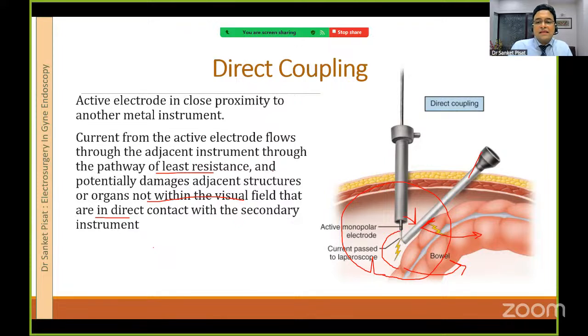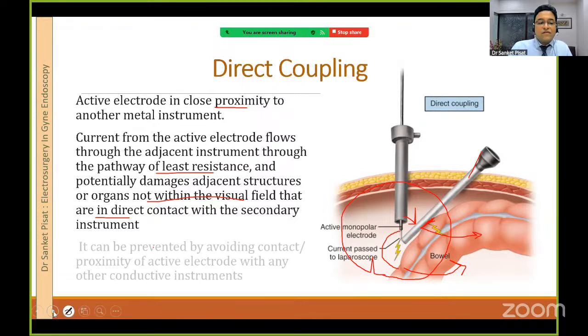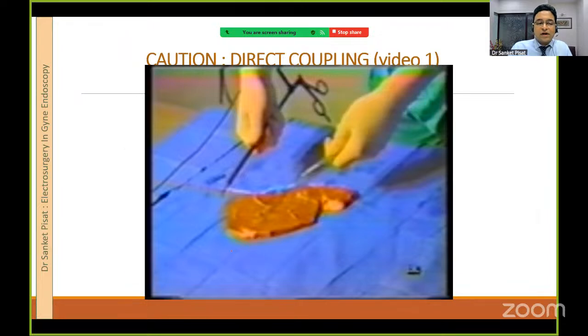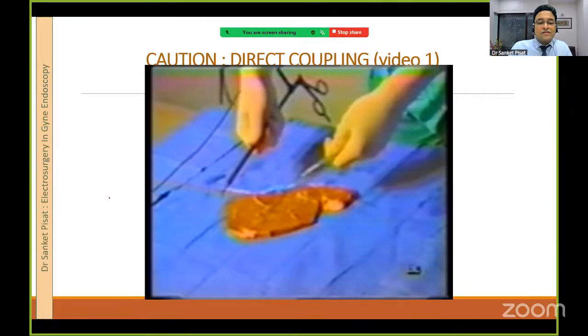So the current is jumping from the primary to the metallic to a vital organ and then going back to the body. Important point to note, the electrode is in proximity to another metal instrument and not directly touching the other instrument. Okay, so this is direct coupling. It can be prevented by avoiding contact or proximity with any other conductive instruments. For example, if you are firing a monopolar electrode, then make sure that you do not have another metallic instrument in close proximity to that one instrument.